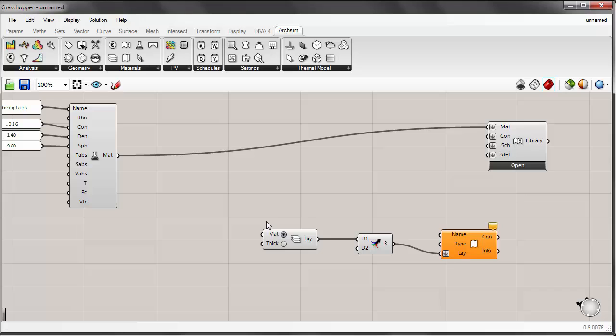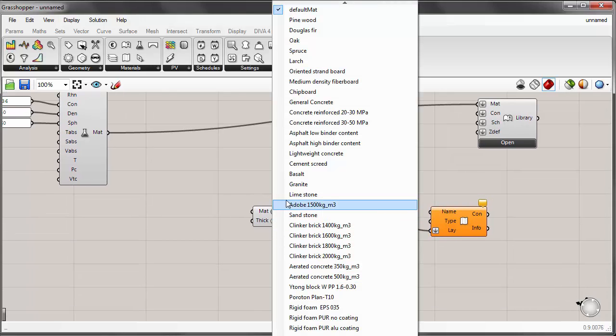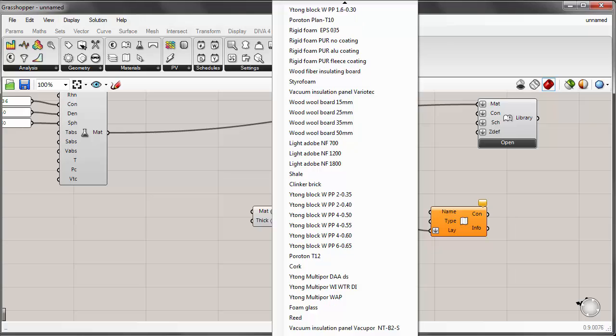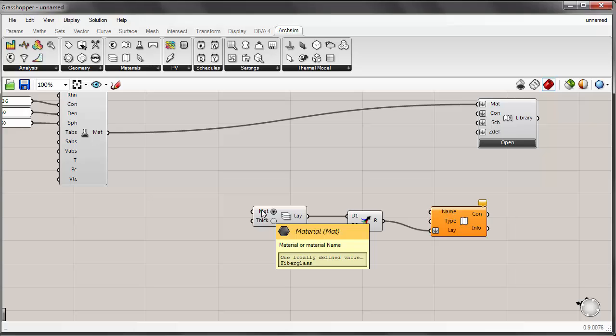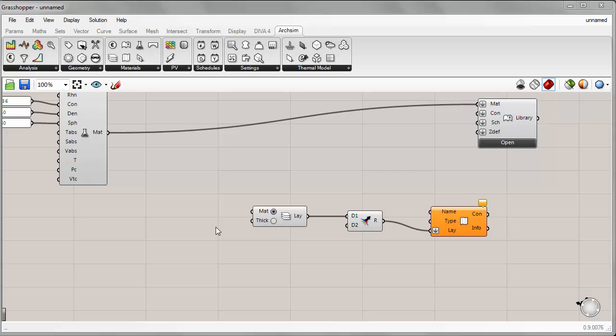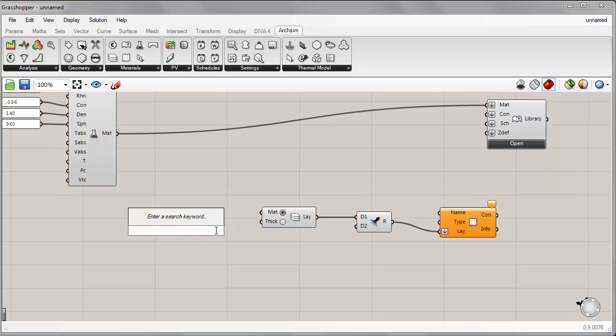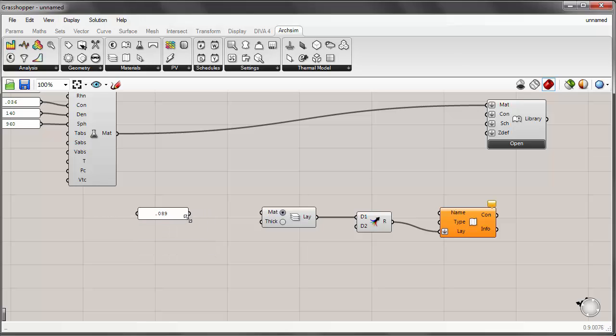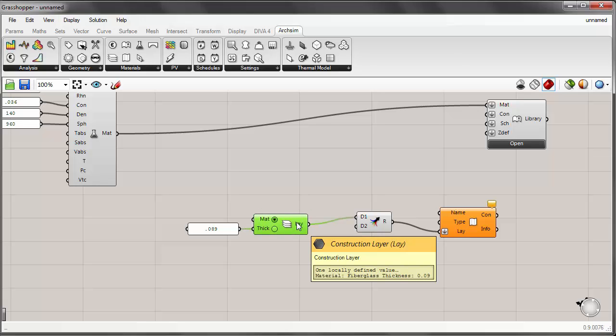Let's create a layer for our fiberglass material. If I click on the material drop-down parameter, we get a list of all the materials in our library — the newest will appear at the bottom. The fiberglass material shows up at the end of this list, and if I select it, it will be input. Now I'll give this material a thickness — let's say this is the cavity of a stud wall, so I'll make this 0.089 meters, which is about 3.5 inches. Hovering over the layer shows fiberglass at a thickness of 0.09 meters.